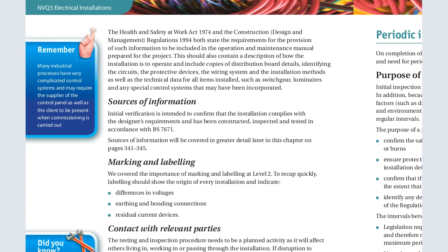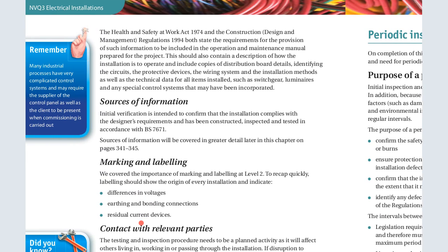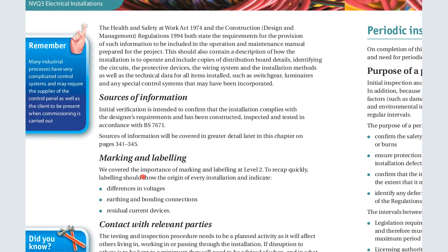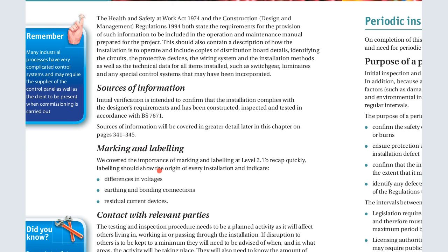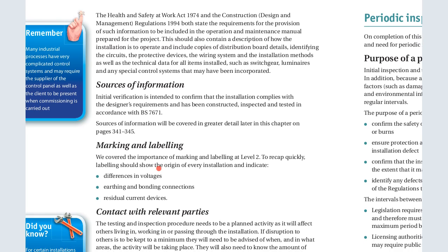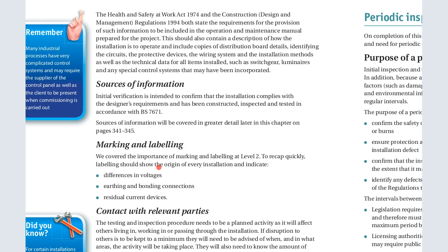So those are among the important safety things that should be carried out before a periodic inspection or test. So the Health and Safety at Work Act, that is 1974, and the Construction Design Management Regulations, that is 1994, both state the requirements for the provision of such information to be included in the operation and maintenance manual prepared for the project. So this should also contain a description of how the installation is to operate and include copies of a distribution board, details identifying the circuit, protective device, and wiring system, and the installation methods.